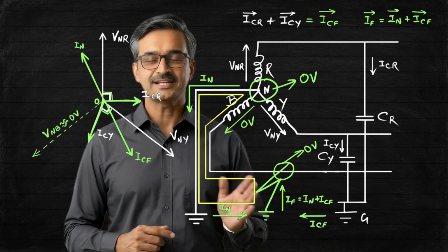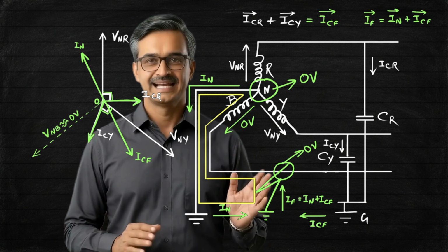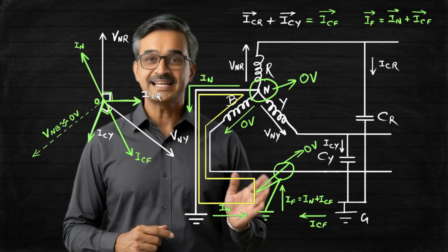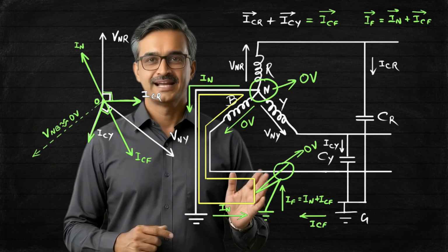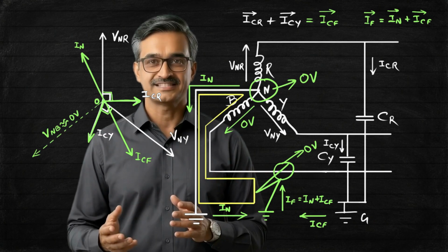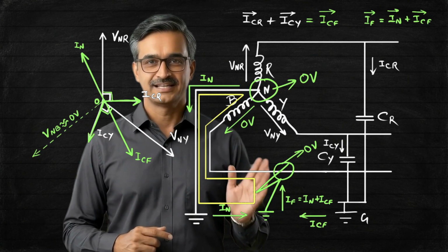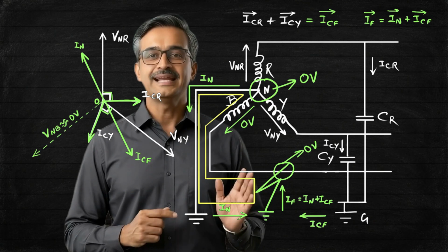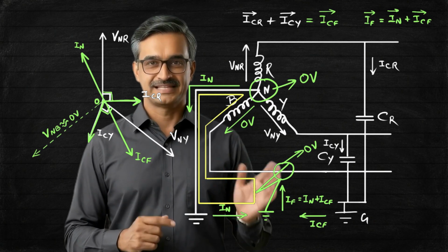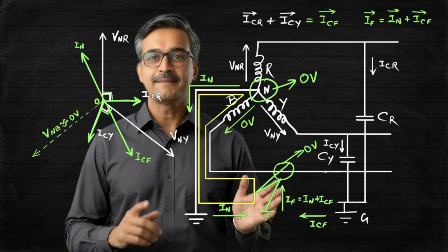Because the neutral current opposes the charging current, the conditions responsible for sustaining an arcing ground are greatly reduced. In other words, the charging current is effectively counteracted by the neutral current supplied through the grounded neutral of the transformer. As a result, the possibility of arcing ground is either eliminated or significantly reduced. This is one of the major advantages of a solidly grounded neutral system.